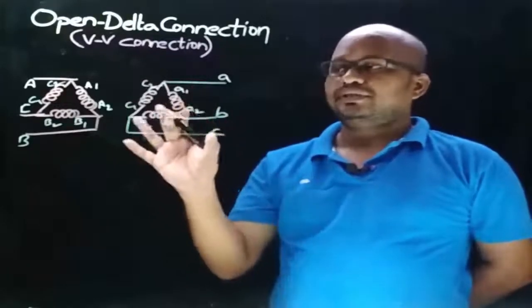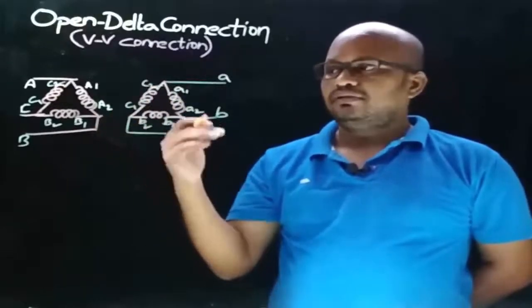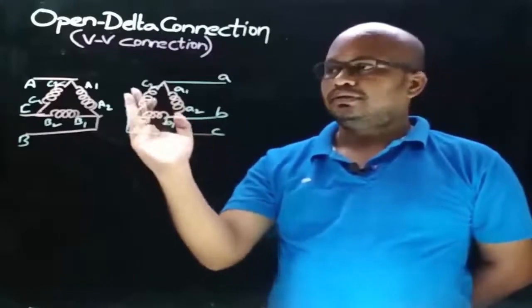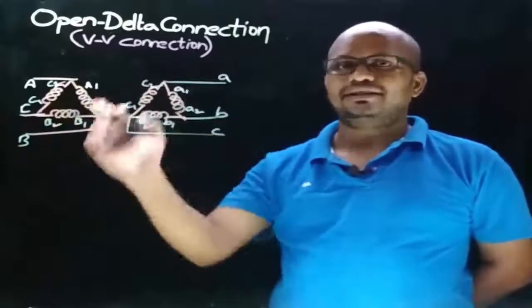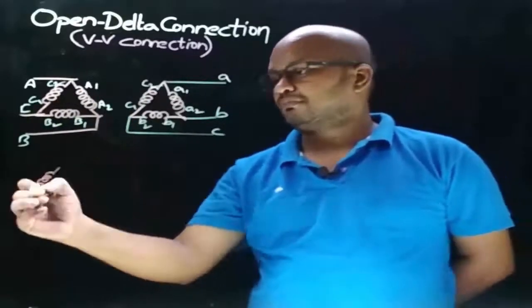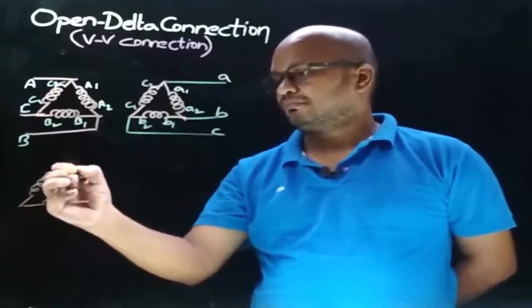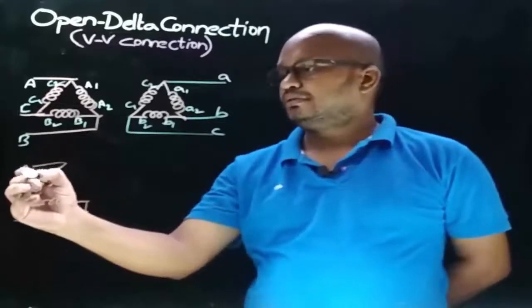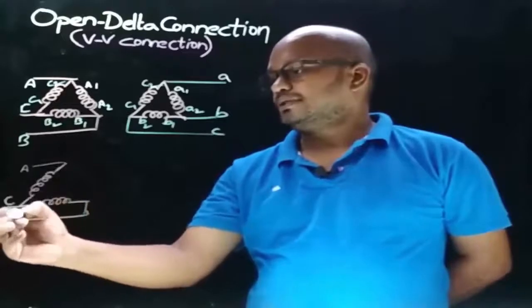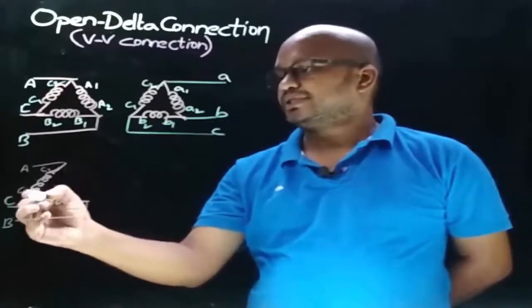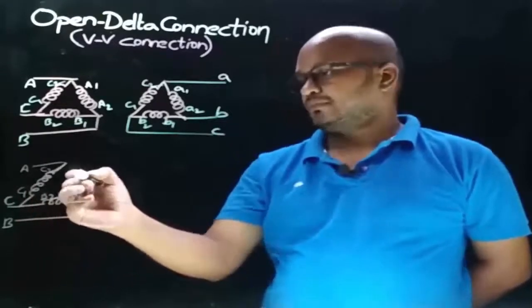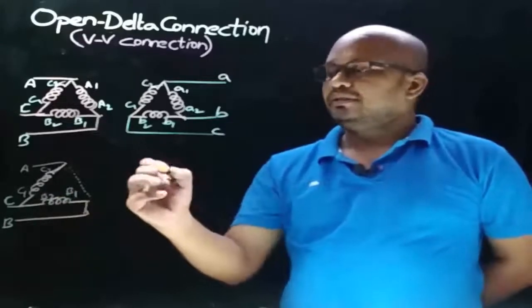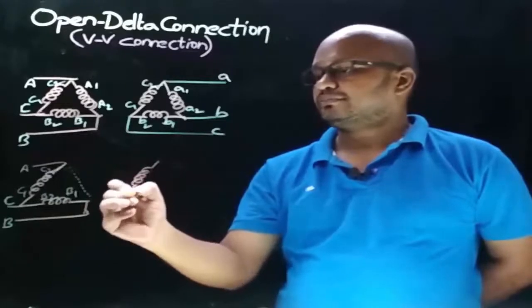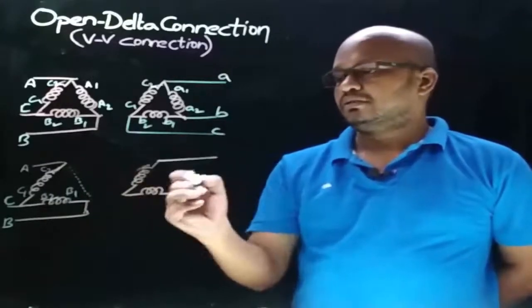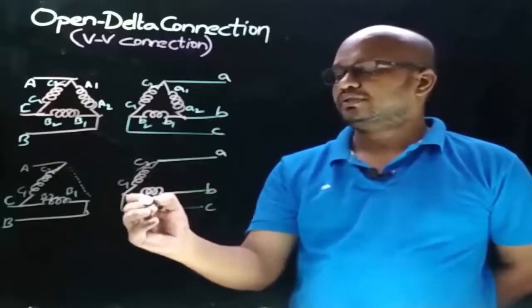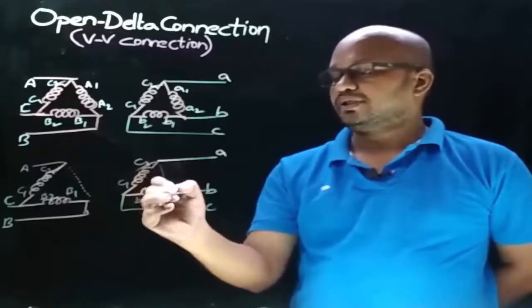Now we assume that one of the transformers in delta-delta connection got failed. Then we remove transformer 1, meaning we must remove the transformer 1 primary winding and secondary winding from this delta-delta connection and observe the resultant winding connection. And the notations here: A, C, and B. This is capital C2, this is capital C1, this is capital B2, this is capital B1. This is the winding which we removed. Similarly, let's draw the secondary winding connections, and let's mark the notations: small c2, small c1, small b2, small b1. And this is the winding which we removed.